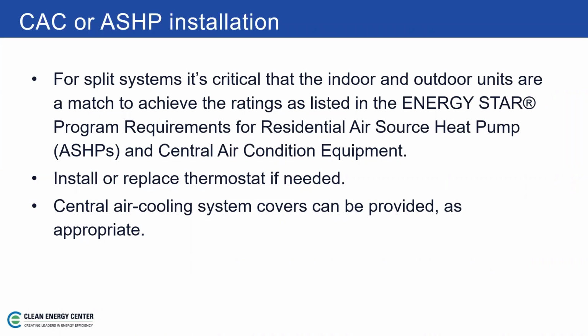So for split systems, it's critical that the indoor and outdoor units are matched to achieve the ratings as listed in the Energy Star program requirements for residential air source heat pumps and central air conditioning equipment. Obviously, thermostats can become an issue, so we want to make sure we either install a new one or replace if needed. And if it's appropriate, central air conditioning covers are allowed to be provided. Just make sure they remember they've got to take them off in the spring whenever they get into air conditioning mode. The covers aren't required, but they're optional if you feel like that would be something the client would benefit from.